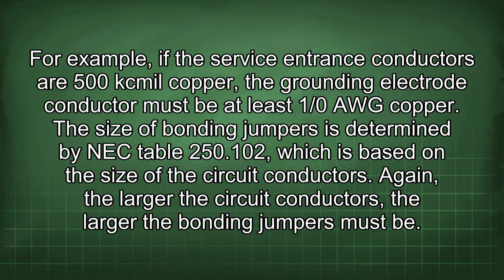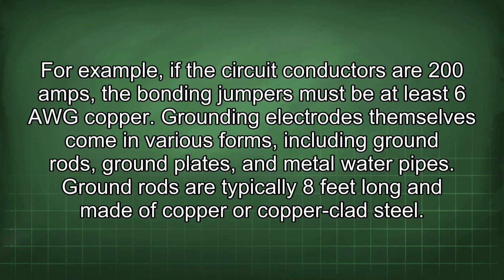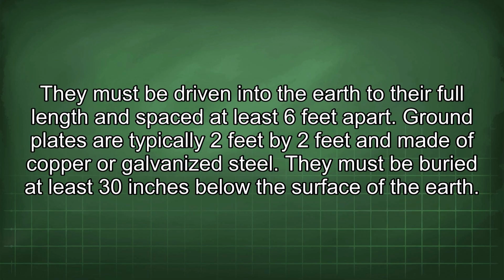250.102, which is based on the size of the circuit conductors. Again, the larger the circuit conductors, the larger the bonding jumpers must be. For example, if the circuit conductors are 200 amps, the bonding jumpers must be at least 6 AWG copper. Grounding electrodes themselves come in various forms, including ground rods, ground plates, and metal water pipes. Ground rods are typically 8 feet long and made of copper or copper-clad steel. They must be driven into the earth to their full length and spaced at least 6 feet apart.